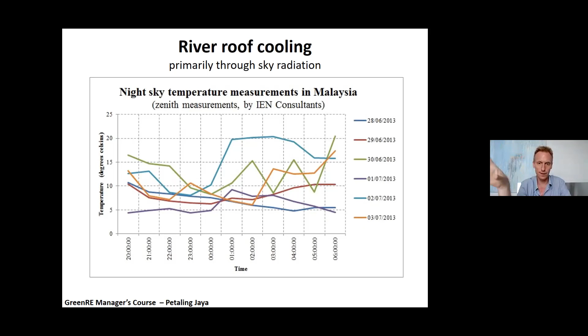So how much cooling can you actually get from the roof at night? We took one of these temperature guns, which measures surface temperature, and pointed it to the sky. Over 6 nights of measurement, we found most nights it was about 10 degrees or maybe even lower. So the sky is actually quite cool, and with our 36 degree hot water, there's a radiation exchange with this 10 degree sky, so you can get most of the heat ejected that way.